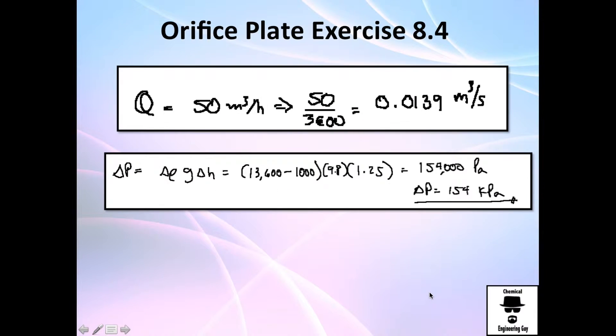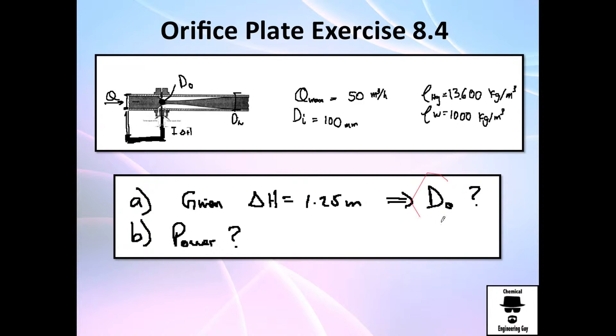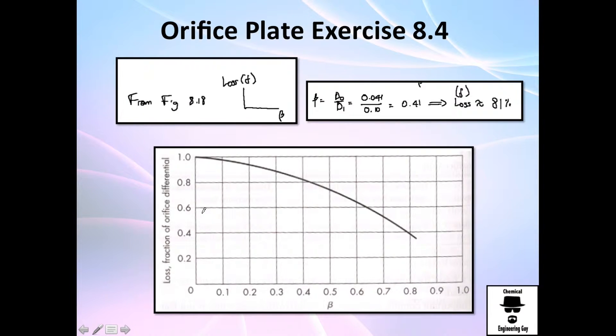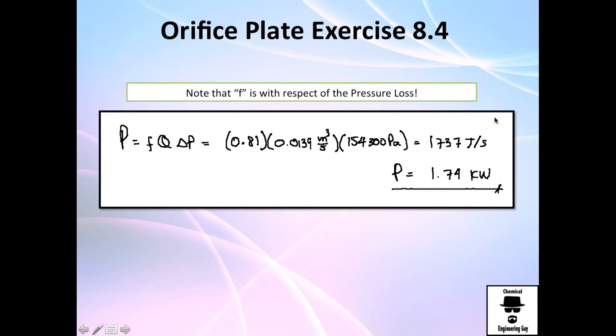Good. And not only I wanted to calculate the diameter, I want to calculate the power requirement. So let me calculate how much friction are we generating. So from this figure, we're going to calculate the loss. So we have beta is the diameter of the orifice divided by the pipe's diameter. We got 0.41, so let me find out 0.41. You go here and I got something about here. So the loss factor is 81%.